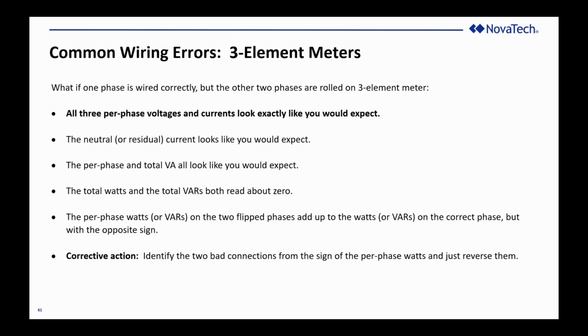What if one phase is wired correctly but the other two are rolled? Okay, that's probably the most common wiring error we see when people call in asking what happened. So in this case, all three phase voltage and current still look normal. The neutral current looks normal. The per phase and total VA look normal. The total watts and the total VARs will read 0. So they're basically going to cancel out.